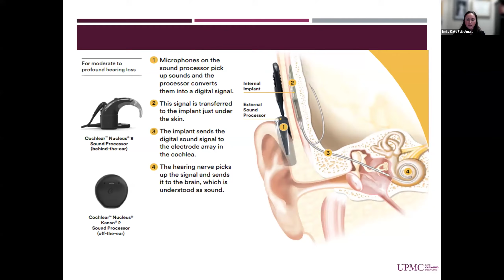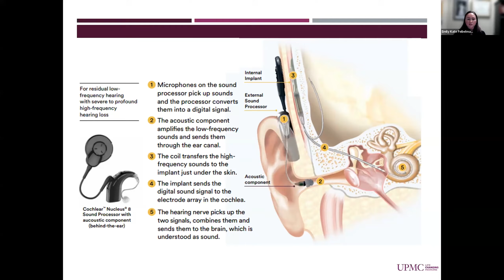So back to that kind of combo device that I talked about. This is called a hybrid processor. The main difference between this and the slide that I just showed and how the traditional cochlear implant processor works is that there's an additional piece called an acoustic component that sits down in the ear. So someone who has pretty good low frequency hearing, but maybe really significant hearing loss in the high pitches that a hearing aid cannot quite help anymore, this would be a great option for them. It's able to combine the use of a cochlear implant for the high frequencies, but also use the low frequency hearing. People who have this device tend to do very well.